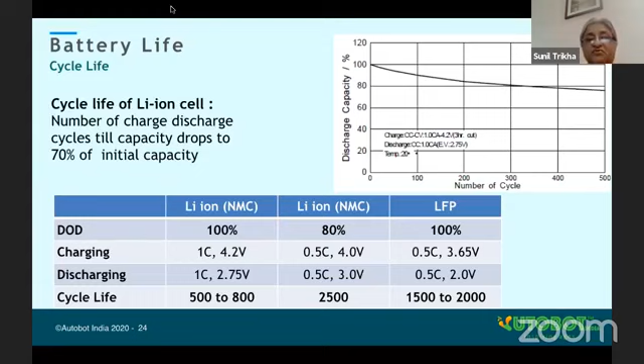LFP cells, even with fully charging and discharging, have a better cycle life. You can get something like 1,500 to 2,000 cycles. This is for comparison. Most importantly, by controlling state of charge and depth of discharge, you can enhance the cycle life of the battery 3 to 4 times. Next, please.